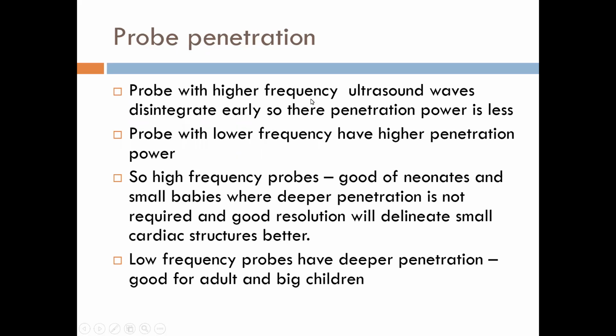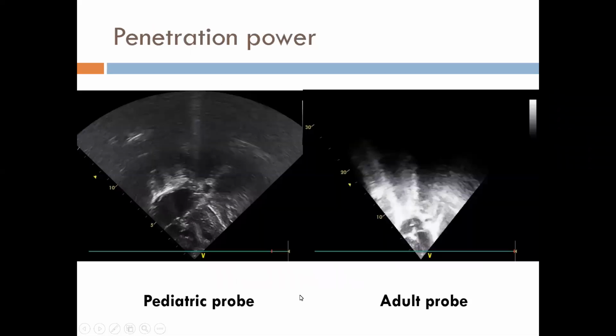The probes with higher frequency disintegrate early, so the penetration power is less. And the probes with lower frequency have a higher penetration power. So the high frequency probes are good for neonates and small babies, where the penetration power is not required and good resolution is required, so even smaller structures can be seen with more clarity. The low frequency probes have a deeper penetration, hence they are good for adults and big children.